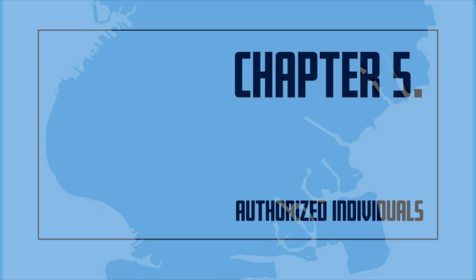3. A master fire suppression piping contractor, A or B, with an S-12 certificate of fitness, can inspect, test, maintain, and repair/replace all fire standpipe and sprinkler system components, and record maintenance, inspection, and test results for examination and evaluation by the fire department. 4. A master plumber with an S-12 certificate of fitness is limited to residential occupancies with 30 sprinkler heads or less, without a booster pump.